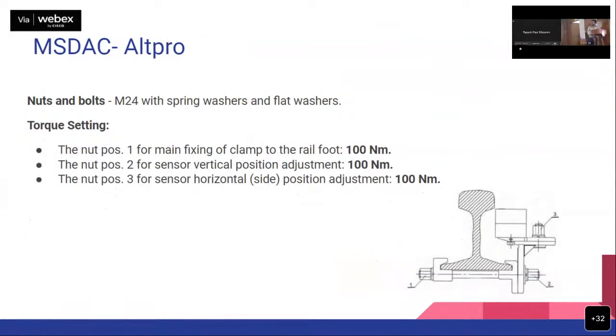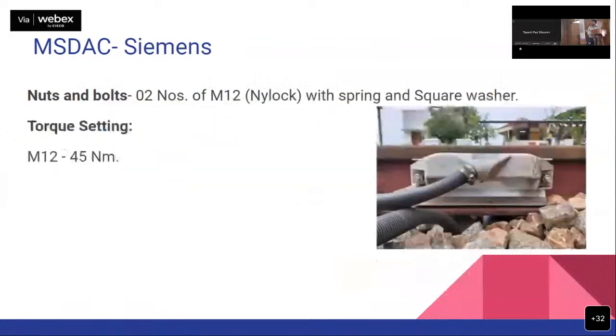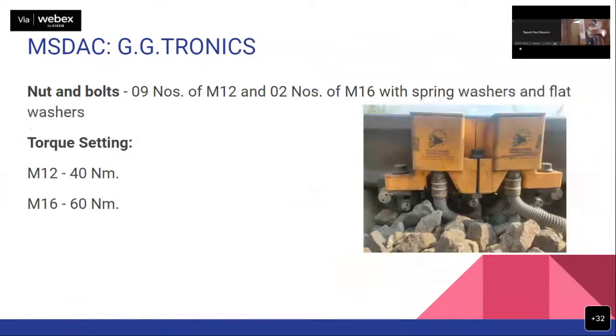This is the same, sir, but in Alt Pro all the torque ranges are the same, like 100 Newton meters for all 3 nut and bolts. In Siemens, this is not a clamp type, this is a hole drill type, sir, so we are utilizing only 45 Newton meters, and only 2 bolts are required here. And this is GG Tronic, sir, it utilizes more number of nut and bolts: 9 numbers of M12, 2 numbers of M16, but they are utilizing spring washers and check nuts, sir.